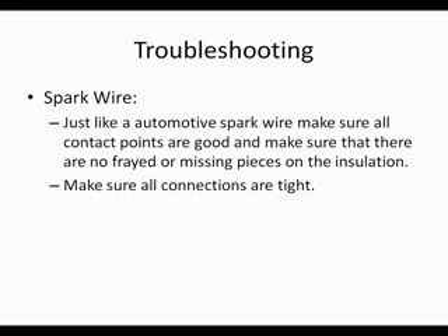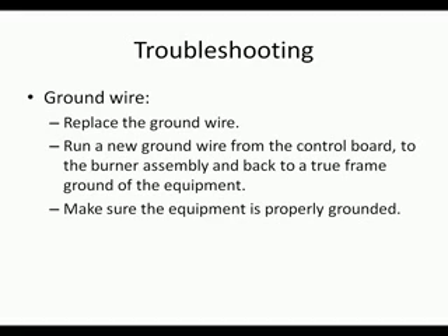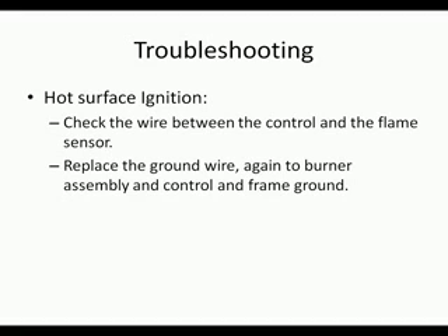When the ignition process fails on a spark ignition system, there are two parts you really want to check: the spark wire and the ground wire. The spark wire is just like an automotive spark wire. Make sure all the contact points are good and make sure that there are no frayed or missing pieces in the insulation. Make sure all connections are tight. Replace the ground wire. Run a new ground wire from the control board to a burner assembly and back to a true frame ground of the equipment. Make sure everything is properly grounded, including the equipment to the building circuit.